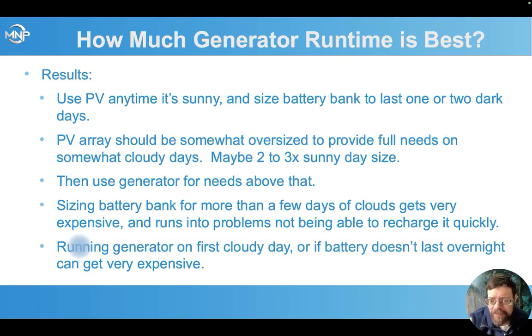If we're sizing our battery bank for a week, that can get really expensive. And we also have the problem that we can't recharge a battery bank that large very quickly unless we've also really oversized the PV array, which is even more cost. And we end up with a situation where we're constantly having a battery bank that's nowhere near full, even though it's very large, and that's not all that helpful.